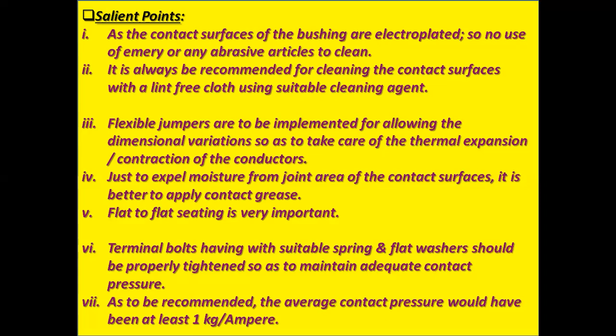Flexible jumpers are to be used to allow for dimensional variations, so as to take care of the thermal expansion or contraction of the conductors. Just to expel moisture from the joint area of the contact surfaces, it is better to apply contact grease. Flat to flat seating is very important. Number 6, terminal bolts with suitable spring and flat washers should be properly tightened so as to maintain adequate contact pressure. As recommended, average contact pressure should be at least 1 kg per ampere. That is 1 kg per ampere of current, you know.